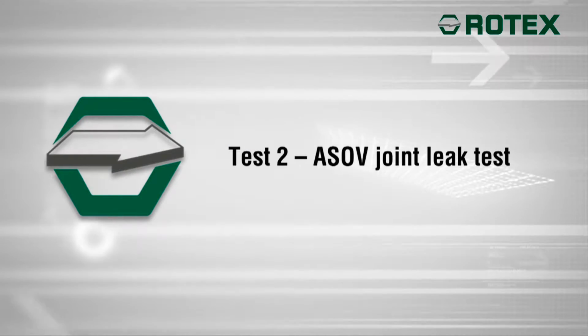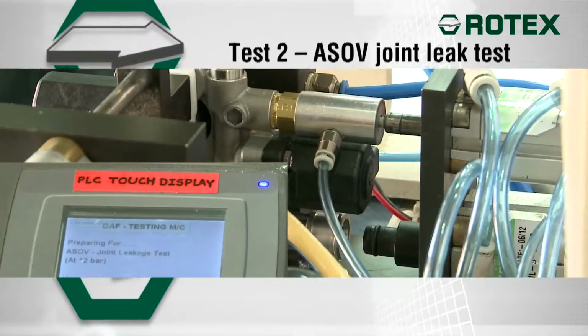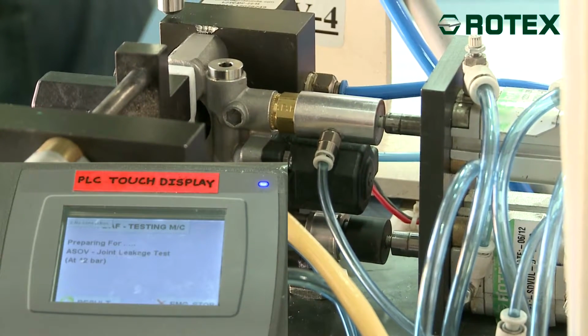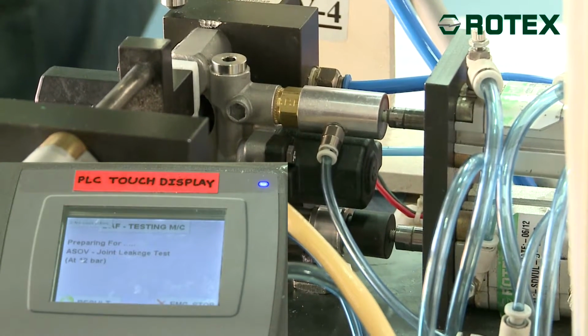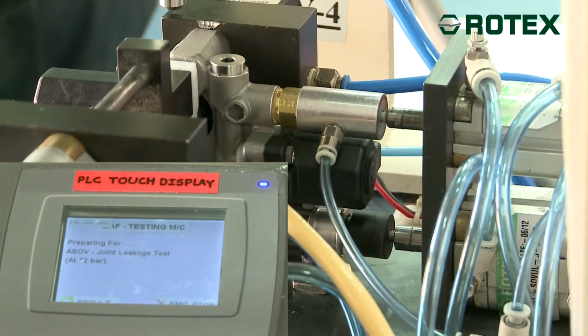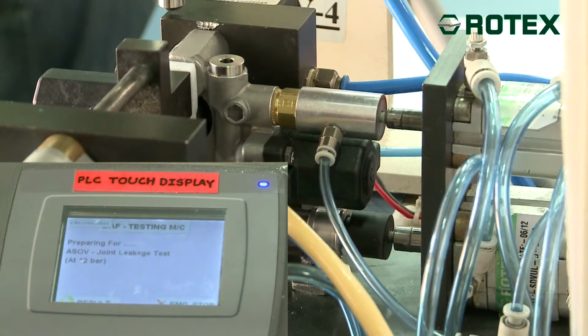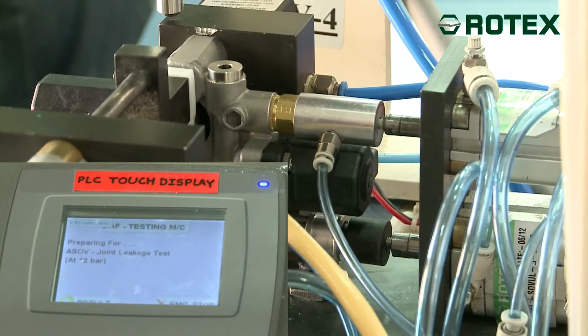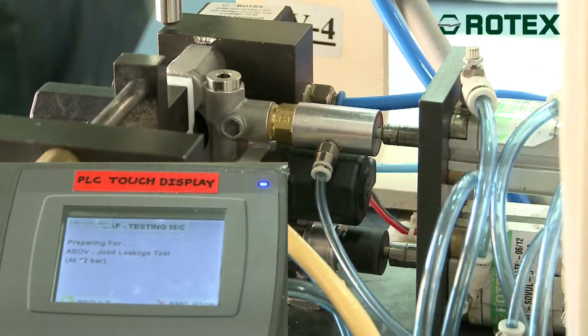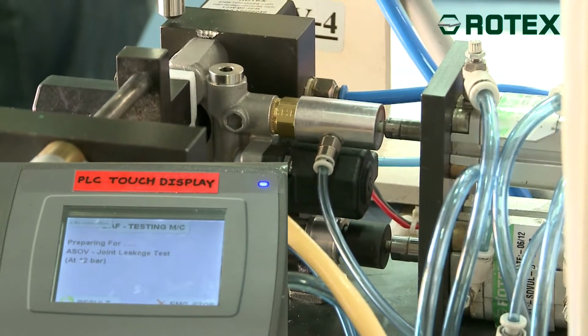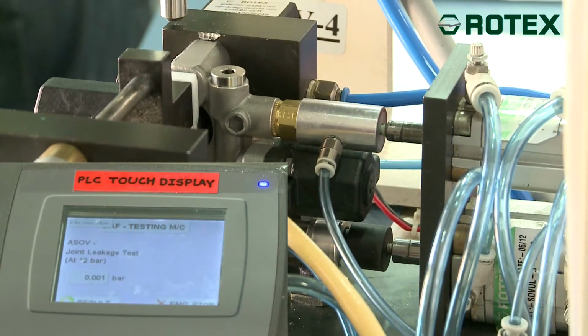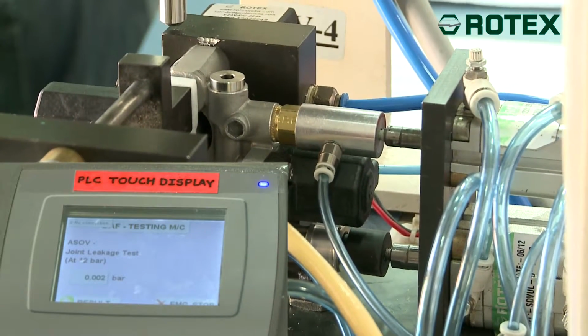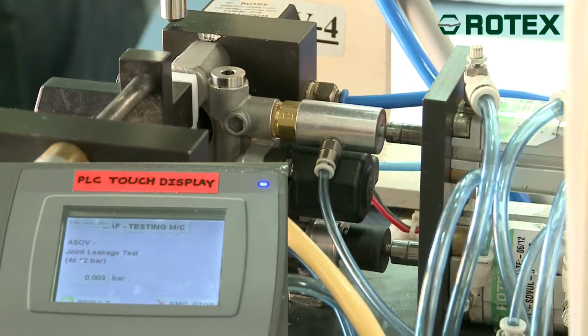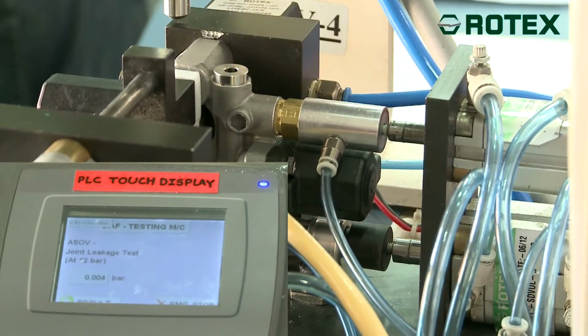Test 2. ASOV joint leak test. Now, ASOV joint leak test will start. This is nothing but external leakage from solenoid valve assembly to atmosphere. Here, the outlet port is blocked and ASOV solenoid is energized, which will fill the complete volume with pressure. Here too, the leakage is measured through pressure decay at 2 bar.